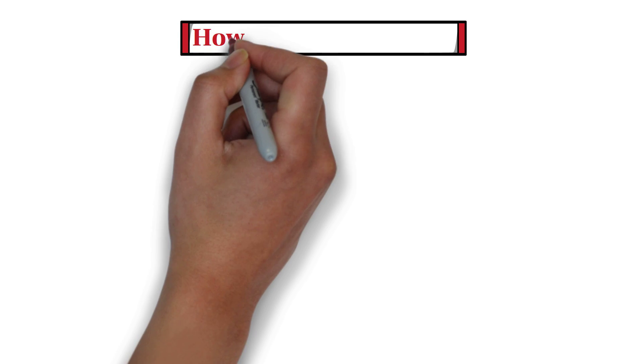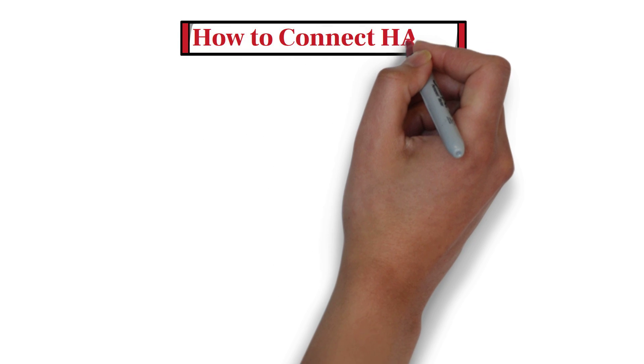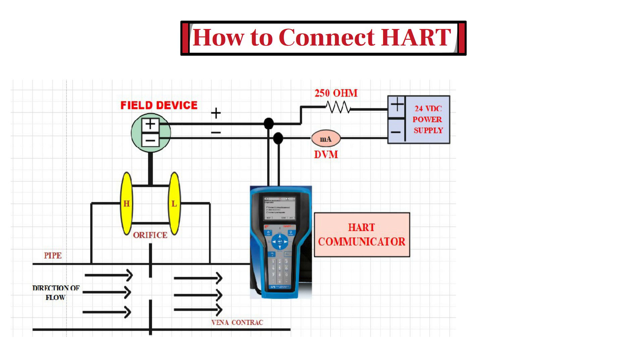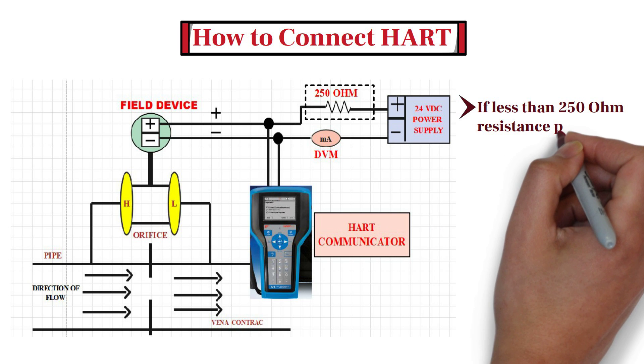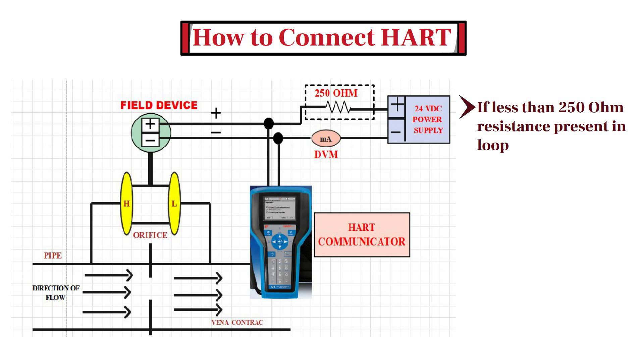First of all, let's start with how to connect the HART Communicator to a transmitter. As you can see, this diagram shows how to connect the 475 field communicator to a HART loop. It is necessary to connect a 250 ohm load resistor if less than 250 ohm resistance is present in the HART loop. For example, when you calibrate the device on bench, it is necessary to connect a 250 ohm load resistor to establish connection with the transmitter.